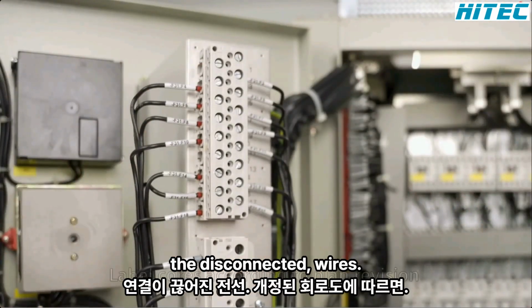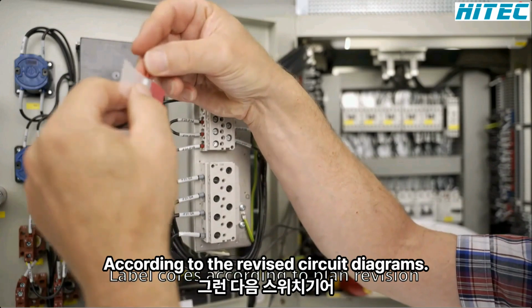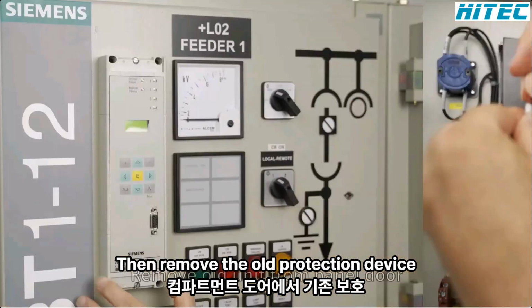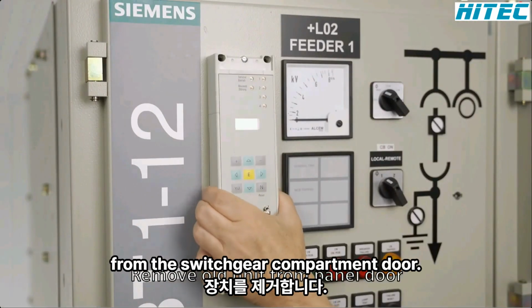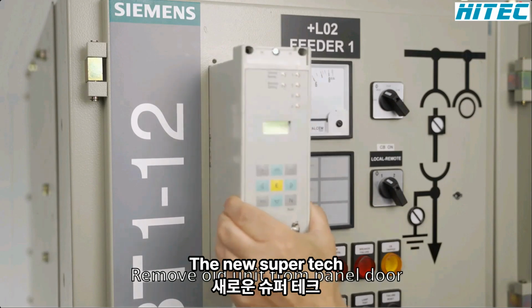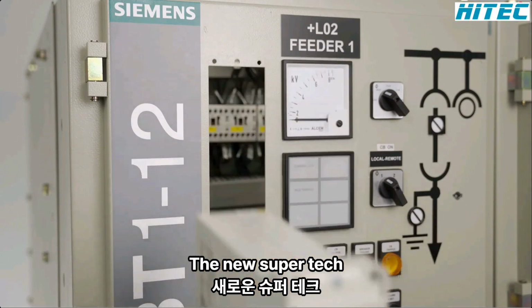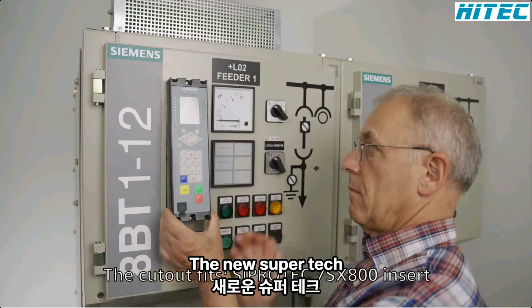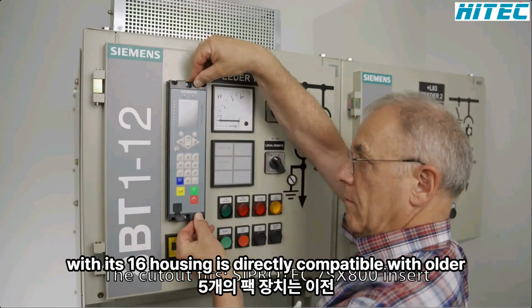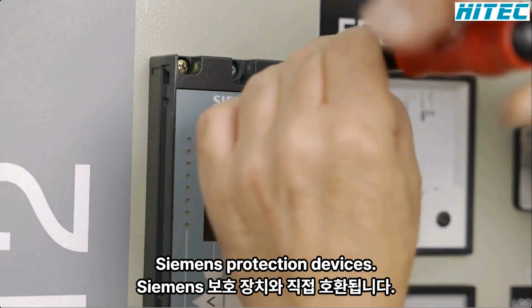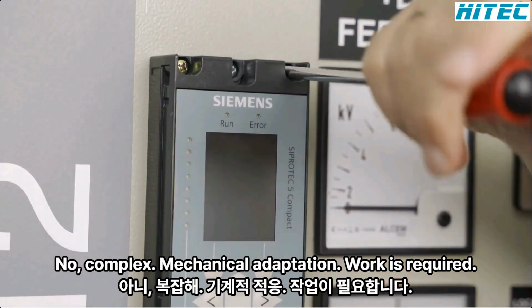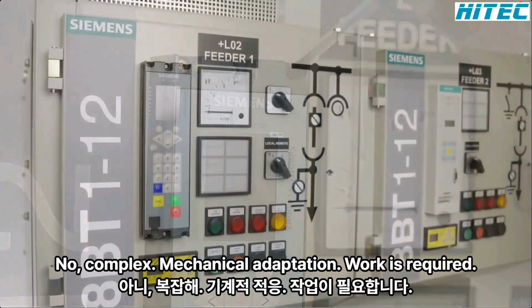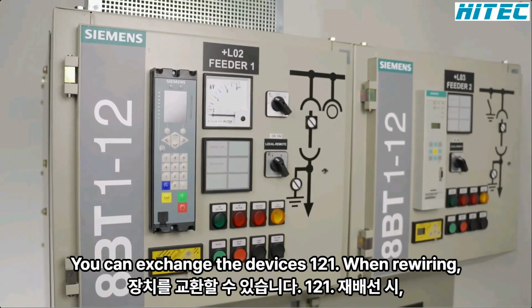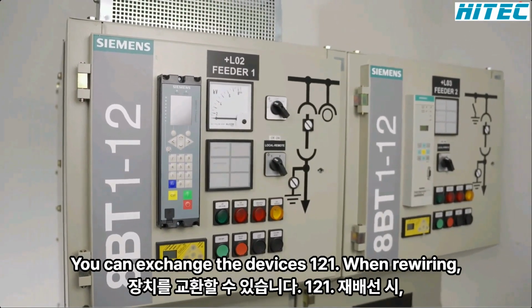Label the disconnected wires according to the revised circuit diagrams. Then remove the old protection device from the switchgear compartment door. The new SIPROTEC 5 compact device with its 1/6 housing is directly compatible with older Siemens protection devices. No complex mechanical adaptation work is required. You can exchange the devices one-to-one.